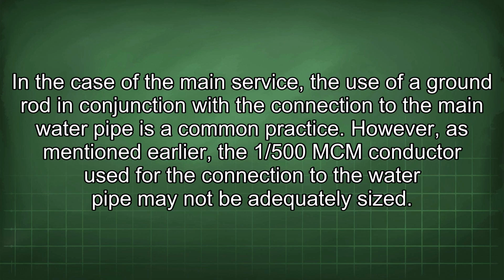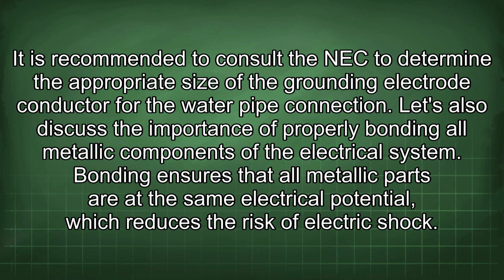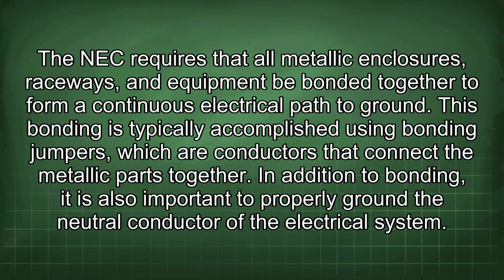However, as mentioned earlier, the 1/500 mcm conductor used for the connection to the water pipe may not be adequately sized. It is recommended to consult the NEC to determine the appropriate size of the grounding electrode conductor for the water pipe connection. Let's also discuss the importance of properly bonding all metallic components of the electrical system. Bonding ensures that all metallic parts are at the same electrical potential, which reduces the risk of electric shock. The NEC requires that all metallic enclosures, raceways, and equipment be bonded together to form a continuous electrical path to ground. This bonding is typically accomplished using bonding jumpers, which are conductors that connect the metallic parts together.